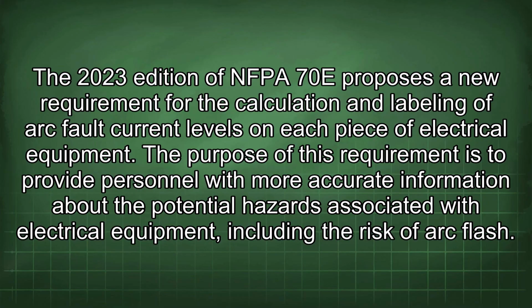The 2023 edition of NFPA 70E proposes a new requirement for the calculation and labeling of arc fault current levels on each piece of electrical equipment. The purpose of this requirement is to provide personnel with more accurate information about the potential hazards associated with electrical equipment, including the risk of arc flash.